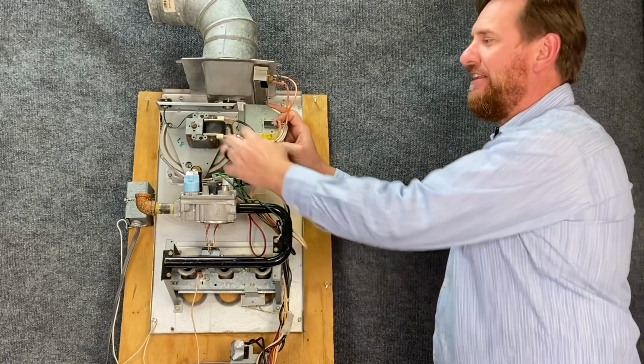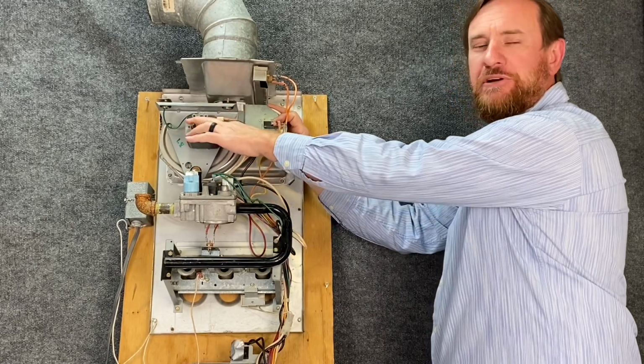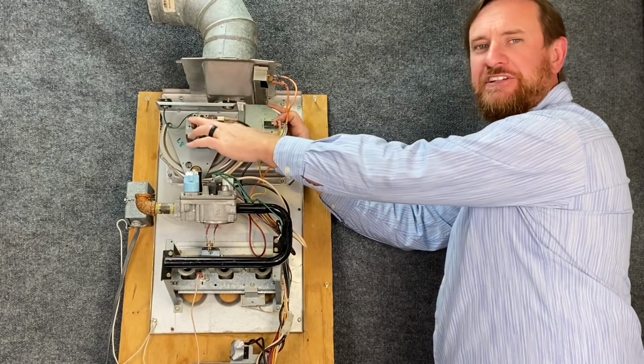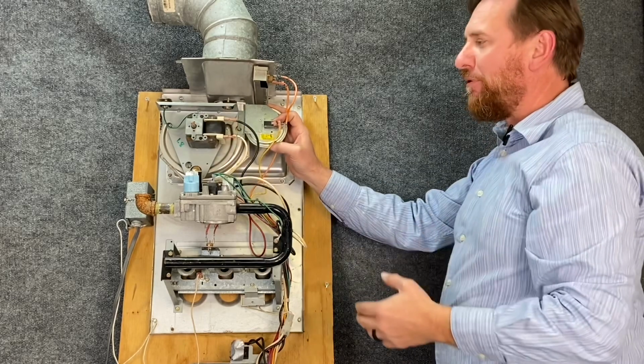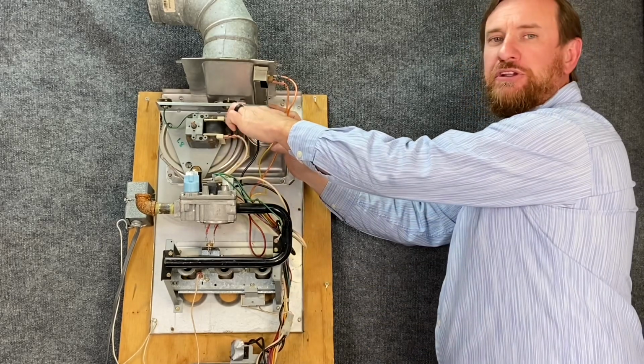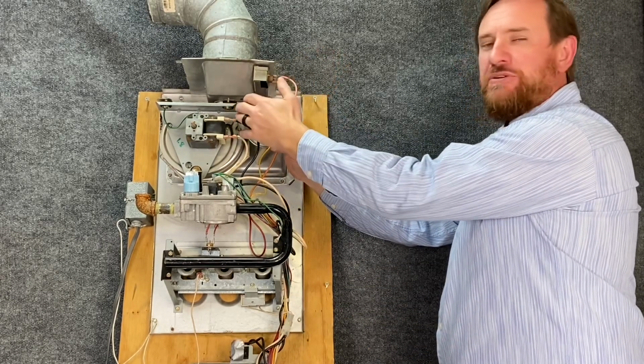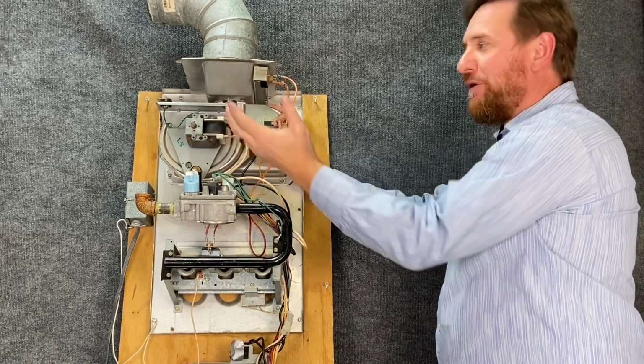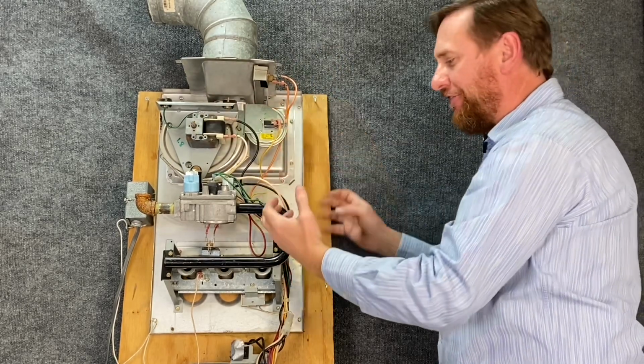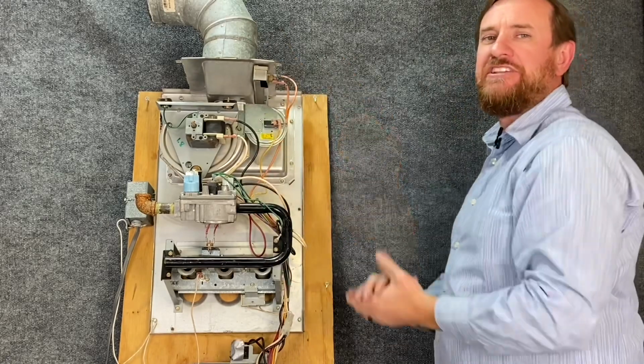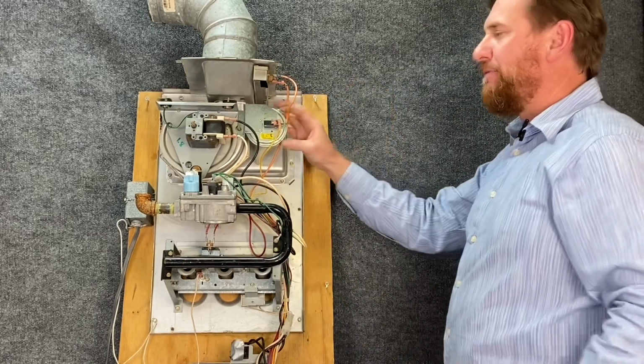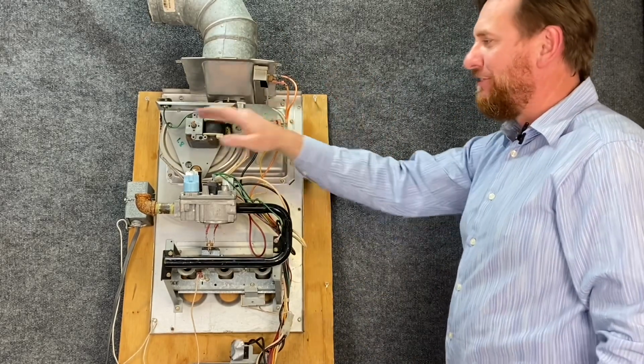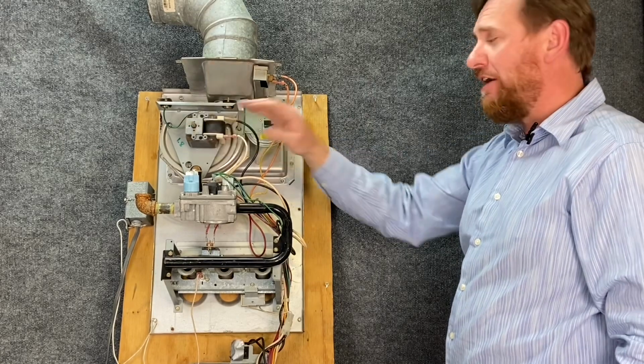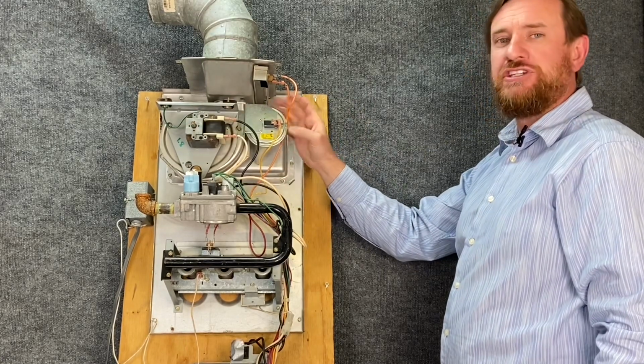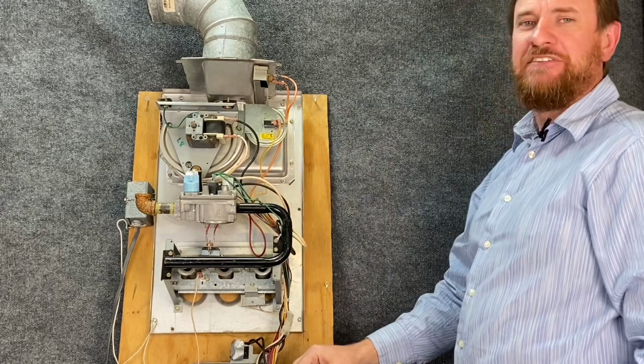In the old days, they had centrifugal switches on these motors. So when the motor spun fast enough, the switch would close. The problem we had was these old motors would rust out. There'd be some kind of an issue with it. The switch would close, but it wasn't actually pulling a draft. The flame would roll out of the heat exchanger and catch the system on fire. So this was the better system that was invented. As this motor is pulling a draft, doing its job, it pulls a vacuum to this pressure switch, the switch closes, and it tells the IFC it's working.